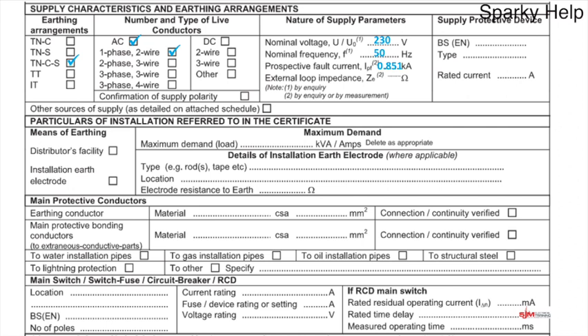Again, this is number 2. It says by inquiry or by measurement. Again, if we inquire to the electricity company for your incoming supply and size of supply, they would quote you the maximum. And in the UK, for a 100 amp supply, a TN-C-S would be 0.35. Incidentally, the fault current for a single phase installation, 100 amp supply, they would quote you 16,500 amps, thereabouts. So as you can see, it's dramatically different.